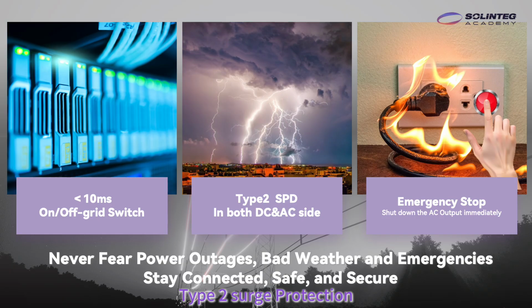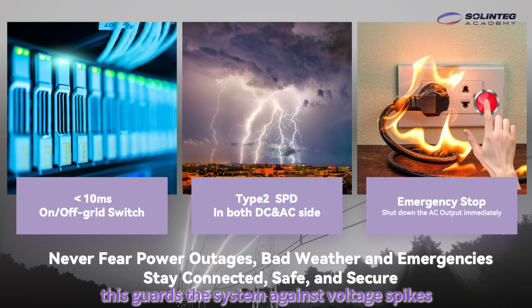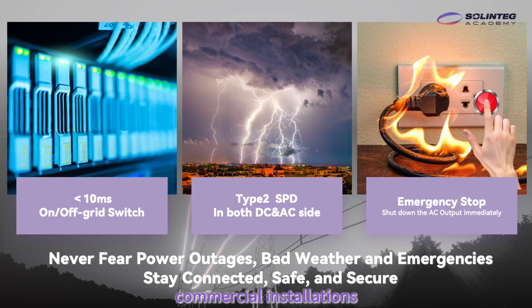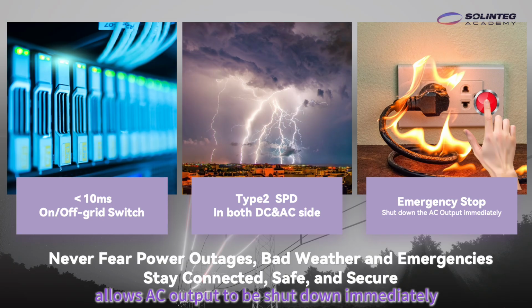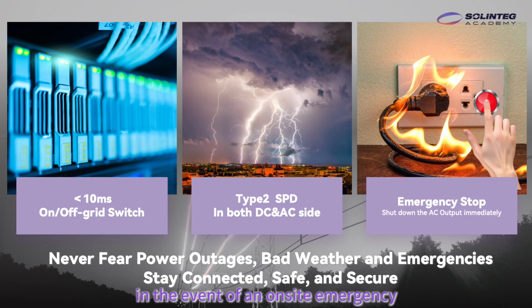Second, Type 2 surge protection devices are built into both the AC and DC sides of the inverter. This guards the system against voltage spikes caused by lightning or grid disturbances, a real concern for rooftop and outdoor commercial installations. And third, an emergency stop function allows AC output to be shut down immediately when needed, giving site operators a fast, reliable response in the event of an on-site emergency.